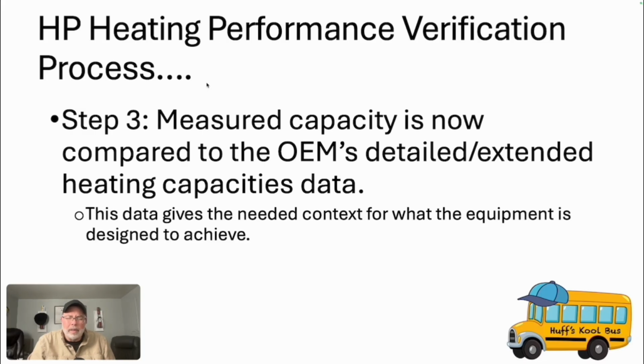It's one thing to say, well, a 2-ton unit should deliver 24,000 BTUs, okay, down to what temperature? I find that every tech has an idea of how many BTUs that should be, and most of them aren't right. Not to mention that it will vary from manufacturer to manufacturer to some degree. Secondly, what about the type of equipment? It's one thing to have a single stage 14 SEER heat pump, but what if we have a 17 SEER variable speed heat pump like the one I have in my house, right?